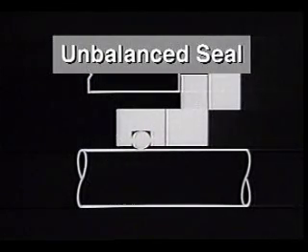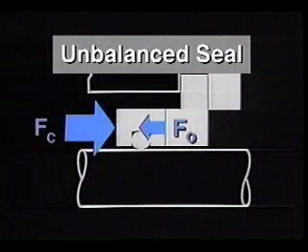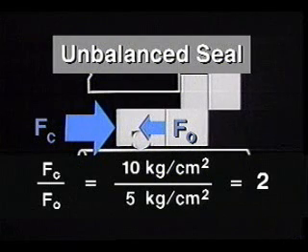With unbalanced seals, when comparing the closing force to the opening force, we find that regardless of the pressure in the stuffing box, the closing force is always at least two times the opening force.